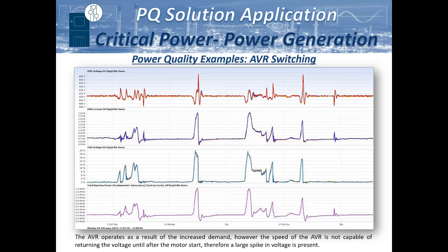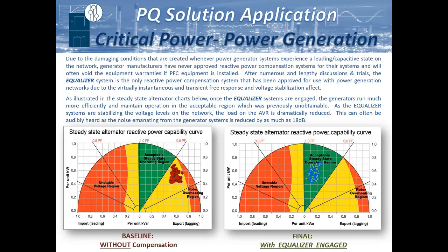And not only that, but you can also see on this AVR, oftentimes by the time the AVR responds, the event is over. So you will get this overshoot and create an overvoltage situation, which can also trip things out. Basically, what the equalizer does is it takes all the load off of the AVR. You can actually hear it in many installations where as soon as you engage the equalizer, we've heard as much as an 18 decibel drop, because it takes all the load and the variability of the load away from that generator and just allows the generator to do what it needs to do.